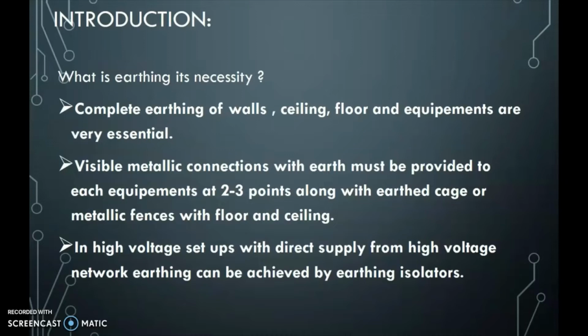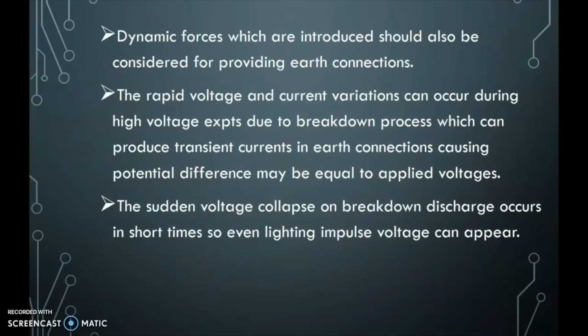A visible metallic connection with earth must be provided to each equipment at 2 to 3 points, along with an earth cage or metallic fence with floor and ceiling. In a high voltage setup with direct supply from the high voltage network, earthing can be achieved by earthing isolators. Dynamic forces which are introduced should also be considered for providing earth connections.